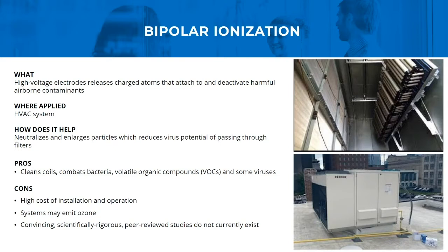They're placed typically within HVAC systems, out of the public view, that type of thing. They neutralize and enlarge particles. So in a nutshell, they attach themselves to viruses or particles in the air, which makes them larger. And being larger, they then get captured within the filter system. A couple of the big pros to bipolar ionization would be that it cleans coils, it combats bacteria, kills off VOCs, which are volatile organic compounds such as odors found within the air, and it does kill off some viruses. Some of the cons to bipolar ionization, however, are the high cost of installation and operation once it's installed.